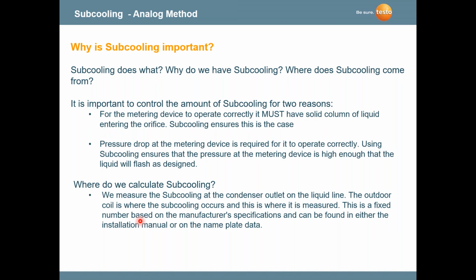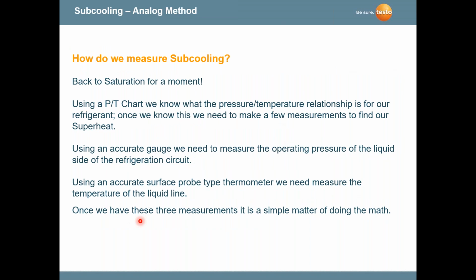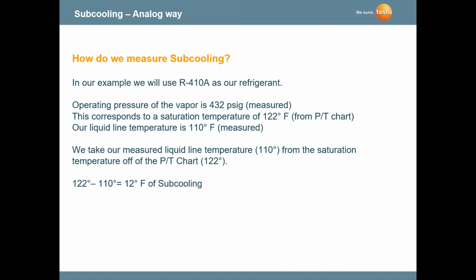Subcooling on the other side is also an important measurement. The metering device needs to operate with a solid column of liquid entering the orifice. So in a way, we do the same thing. We may be using PT charts. We have a high pressure gauge to measure the high pressure side. And again, if we use 410A as an example, here we have 432 PSIG, which we measure. We convert that to 122 degrees Fahrenheit from the saturation temperature chart. We still have to measure our liquid line, and we do the calculation to get the 12 degrees Fahrenheit subcooling.